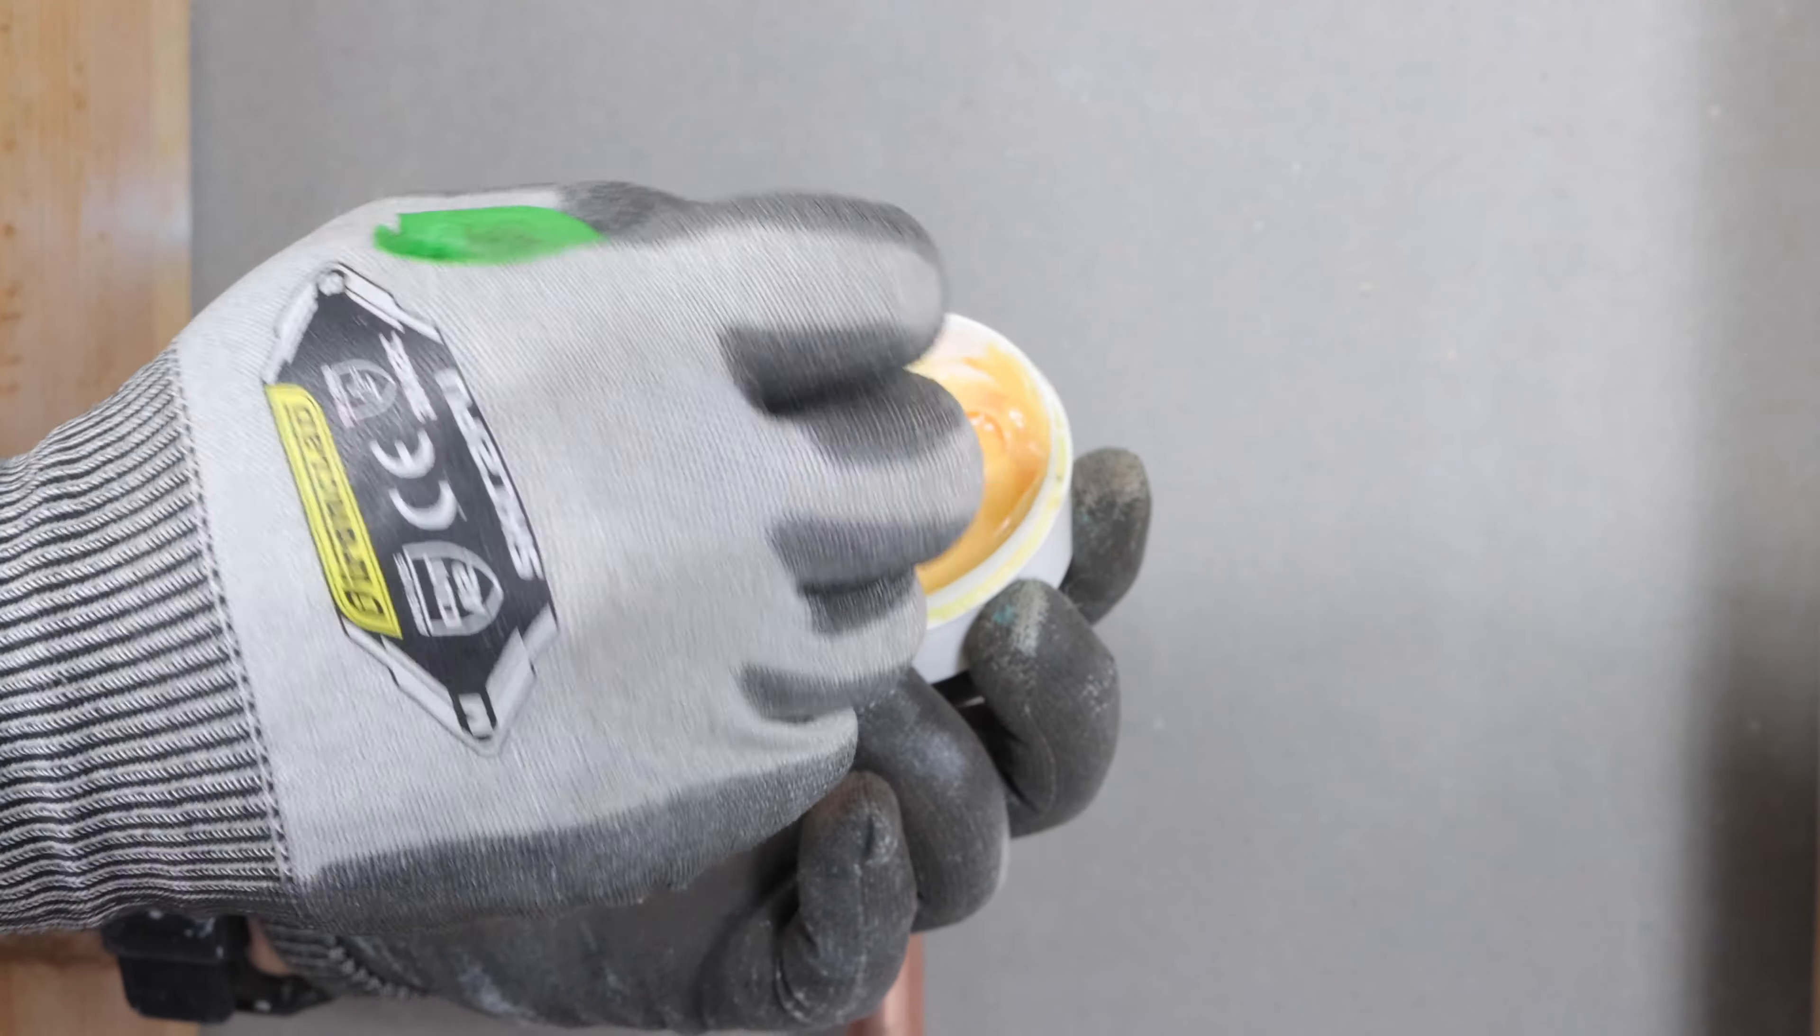Then I recommend using Oatey H-20 water-soluble flux. I mix that up really well in case the salts settle to the bottom of the container. And the reason why I like this is you can use it and you don't have to flush out your system unlike with other flux.